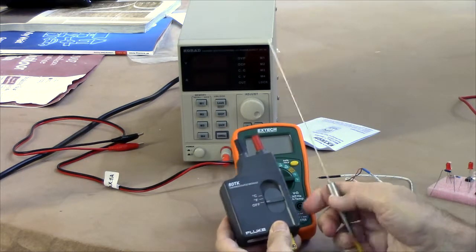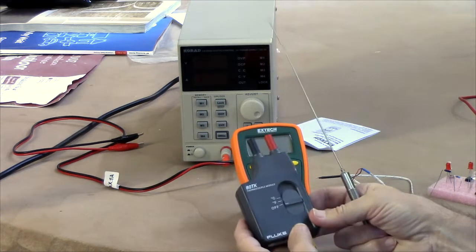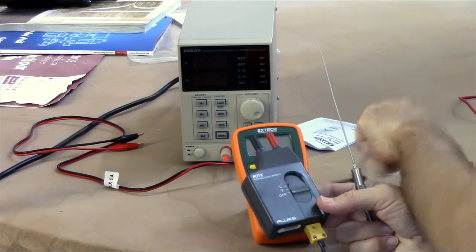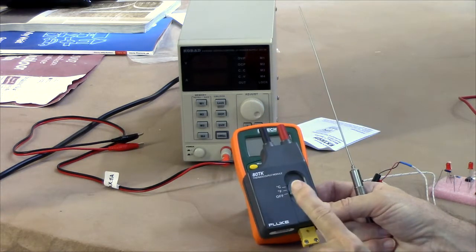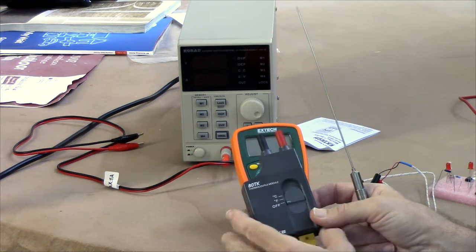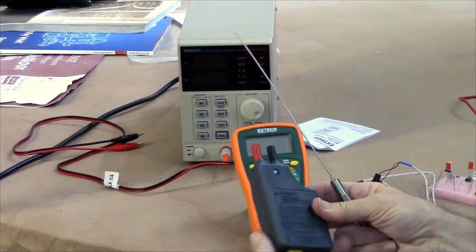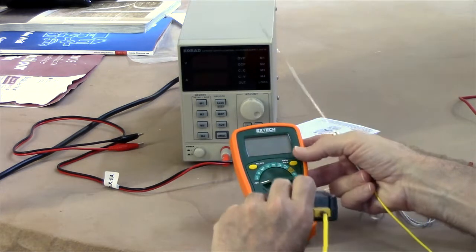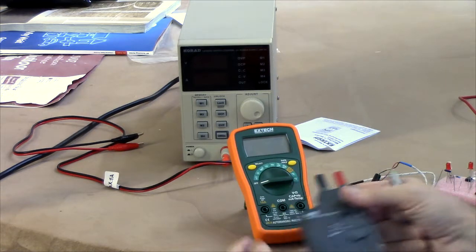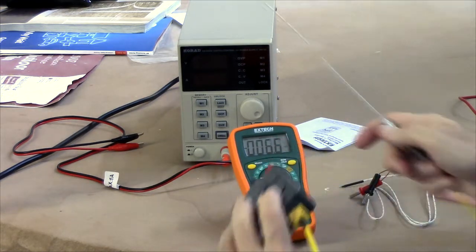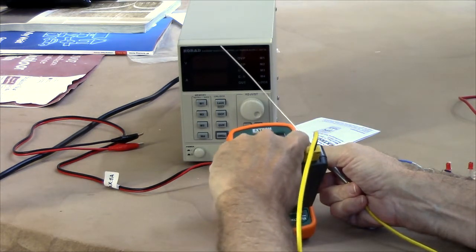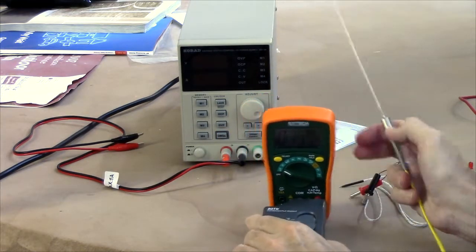Here, I've got one of these. This is a Fluke thermocouple module. What this does, and there's the thermocouple probe that I've got to go with it. I think it came with one like that. And I bought this separately. That's my best recollection. What this does, is this will convert temperature to one millivolt per degree. So I plug that in and we're going to assume for the moment that the voltage readings are accurate on this. And it just plugs right in there because it's the standard spacing. You can see that.